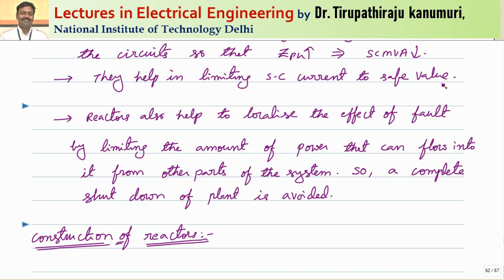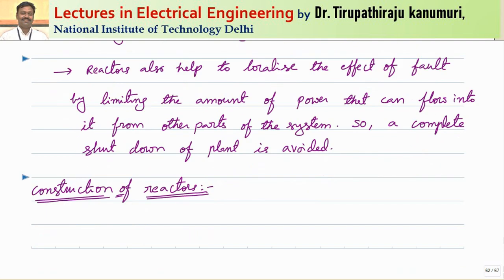Increasing Z per unit ensures the short circuit MVA does not exceed the rating of existing circuit breakers. Another advantage of using reactors is that they help limit the short circuit current to a safe value, so that transmission line conductors and other equipment will not be damaged due to overloading. This also helps localize the effect of a fault by limiting the power that can flow into the fault from other parts of the system.